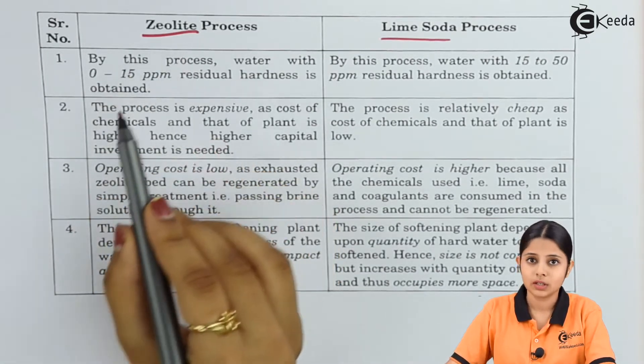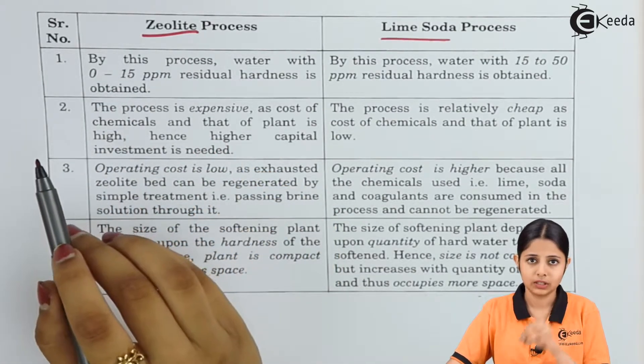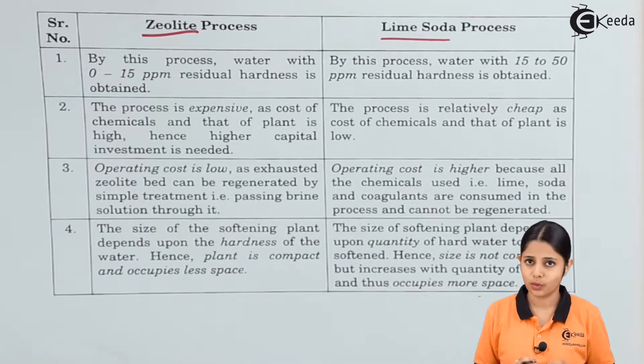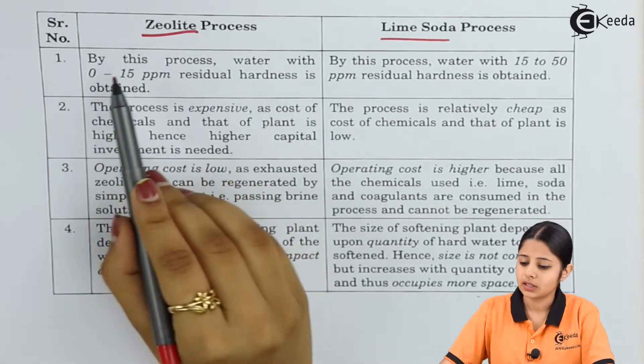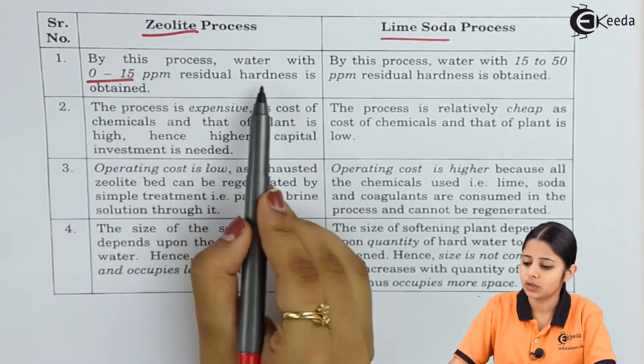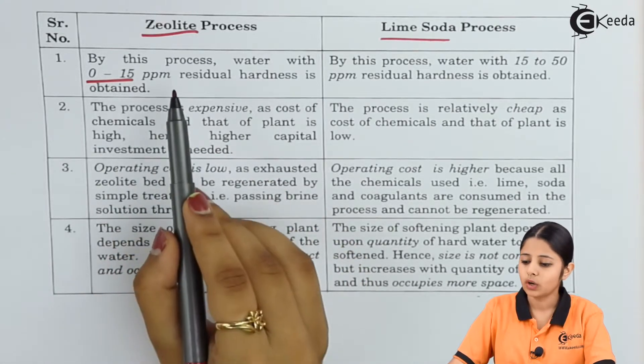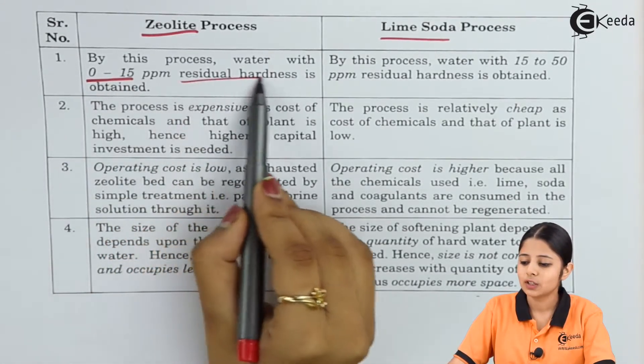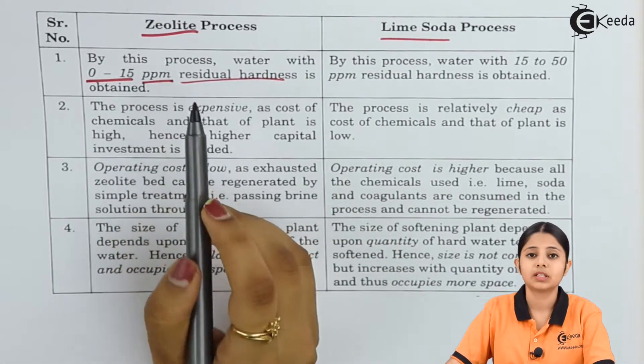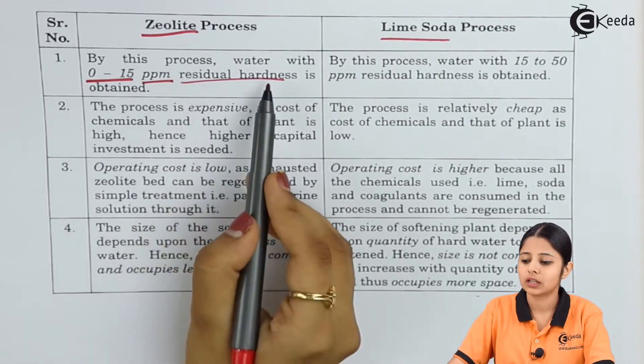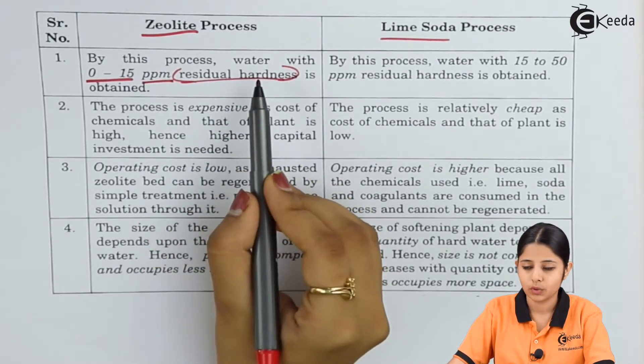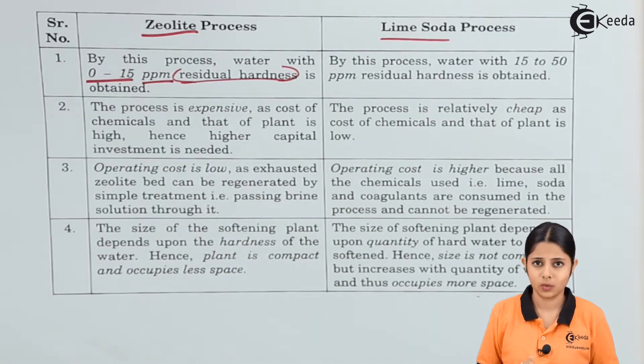In the zeolite process we add zeolite or permutite inside the water. In the lime soda process we add lime and soda. The first comparison point: the zeolite process produces water with 0 to 15 ppm residual hardness. PPM means parts per million, and residual hardness refers to the remaining impurities — the soluble salts still present in the treated water.